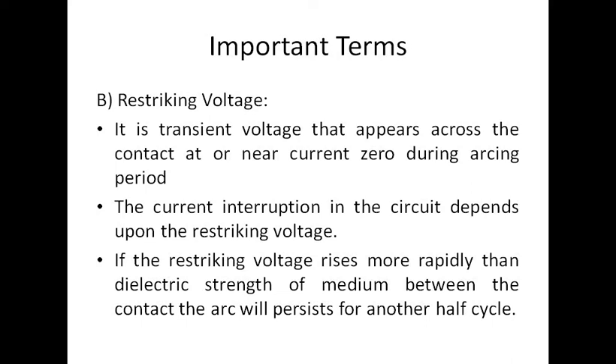To understand properly, restriking voltage is the transient voltage that appears across the contacts at or near current zero during the arcing period. The current interruption in the circuit depends upon the restriking voltage. If the restriking voltage rises more rapidly than the dielectric strength of the medium between the contacts, the arc will persist for another half cycle. In the next half cycle, the arc occurs again — this is called the restriking concept, and the voltage that appears across the line is called the restriking voltage.